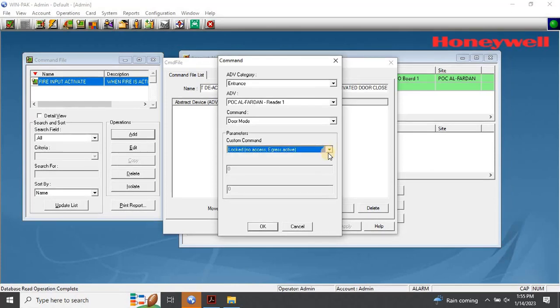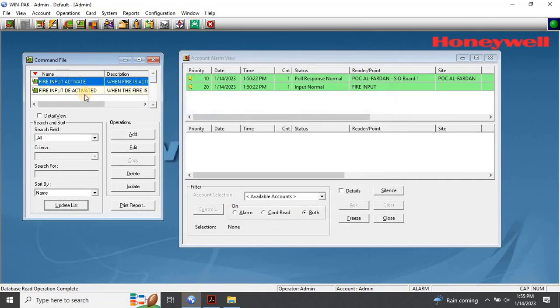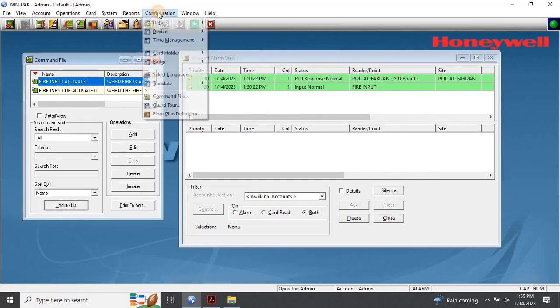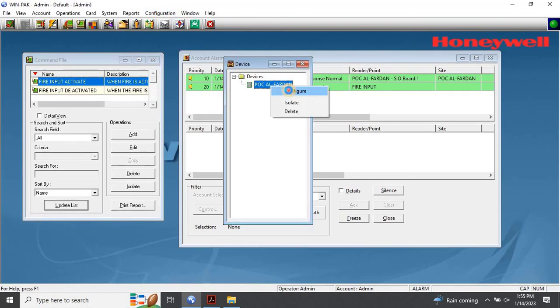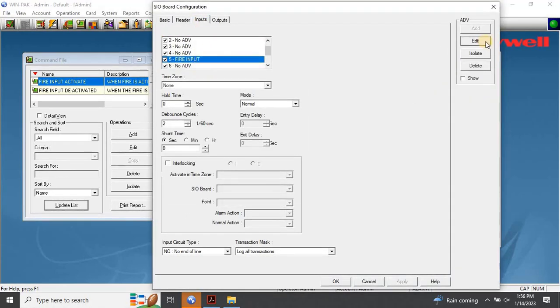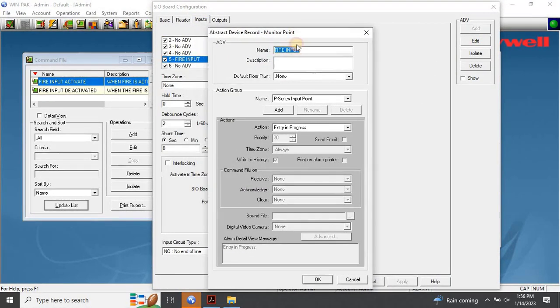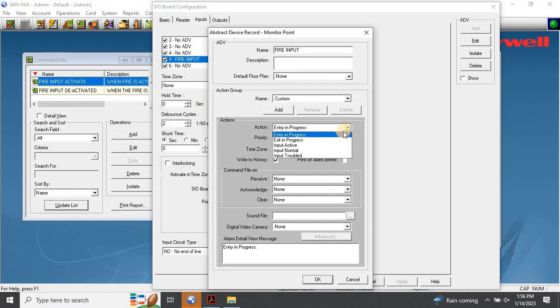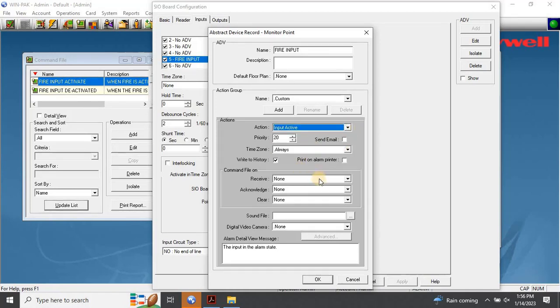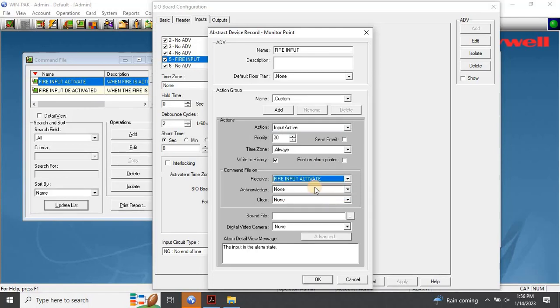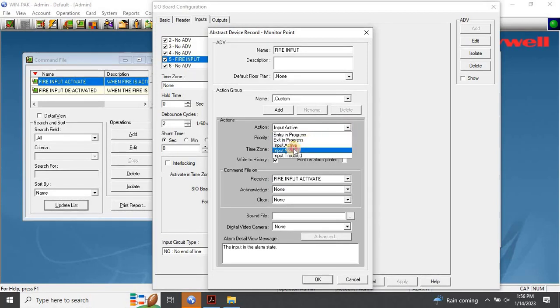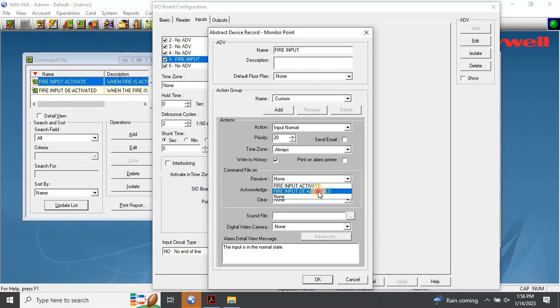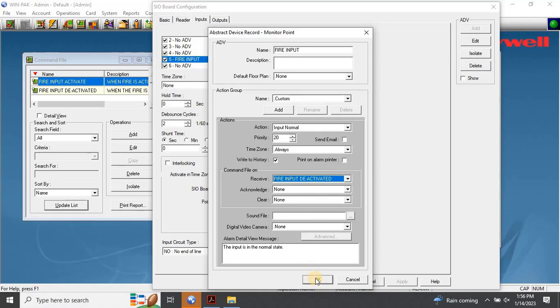Once the command file creation is complete, the next step is to assign these commands to the input. To do this, go to the SIO Board Input Terminal configuration and change the action group name as Custom. Then change the action to Input Active, and select the command file on Receive As — the Fire Input Active command that you just created. Once the settings are complete, click OK to close this window.